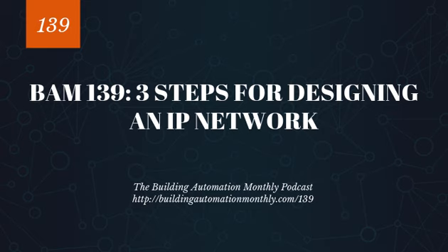With that being said, we move on from there to layer 4, which is our transport layer. Now, the transport layer is where all the ports exist. Now, ports are different than the physical ports that we talk about in the data link layer. This is logical ports. These are ports that exist for applications. So the important thing to understand here is this is where you run into issues where your server doesn't communicate to your supervisory device because you don't have UDP port 47808 open, which is the BACnet port, by the way.